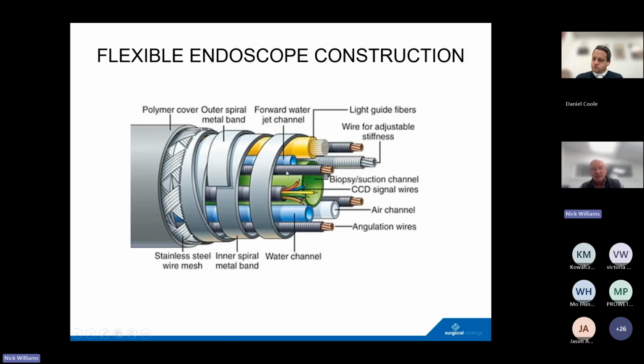And then inside this, you then have your channels, so air, water, biopsy, and suction. You have a light guide to take the fibers down, to take the light down so you can see. You need obviously to then take the image back, which will either be via an optical fiber optic bundle, or normally nowadays by electronics, so CCD or CMOS chips at the tip, and this goes back via these wires. And then there are angulation wires, in this case 4. There are other channels such as forward water jets, and there could be auxiliary channels. So this gives you an example of the complexity of everything that's inside the internal anatomy, if you like, of the scope, which is quite significant.